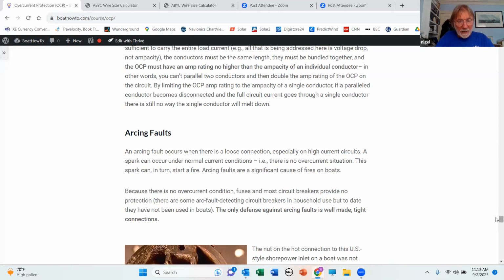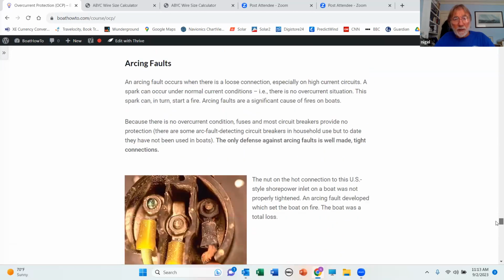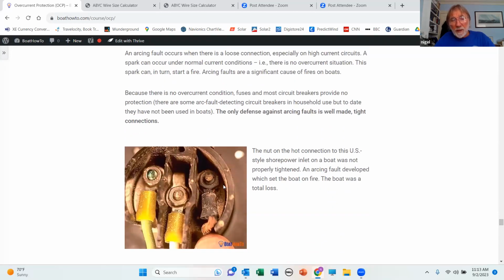We have a different way of generating heat, which is a loose connection. If we have a loose connection, we can get a spark. In this case, this nut wasn't done up. This is a shore power inlet on a boat. And even though there's no overcurrent situation, so a fuse or circuit breaker is not going to trip, we can still start a fire because of this loose connection, this arcing fault. And in this case, the boat burned to the waterline simply because that one nut wasn't tightened up adequately.